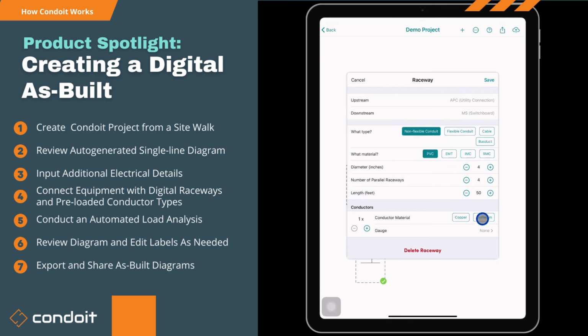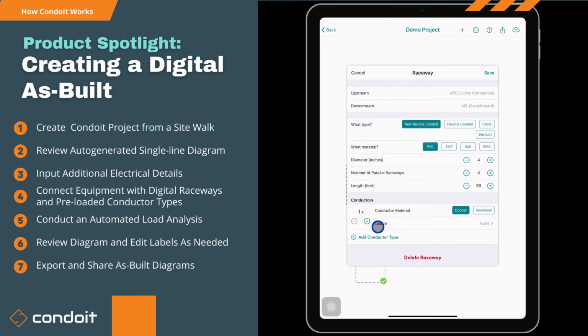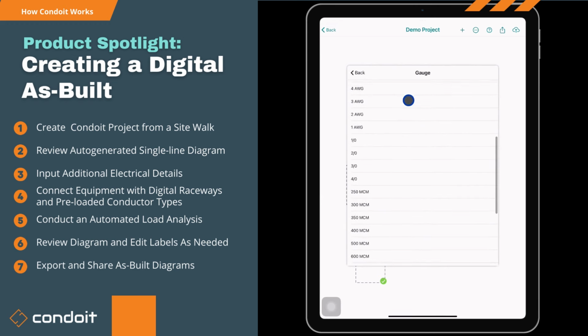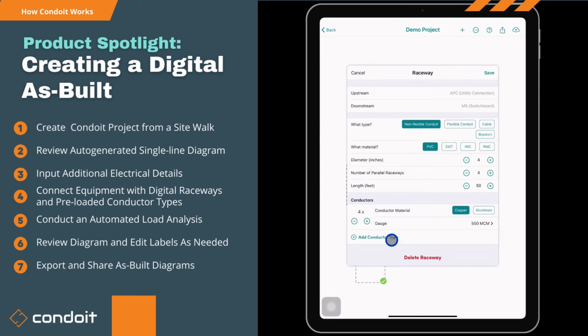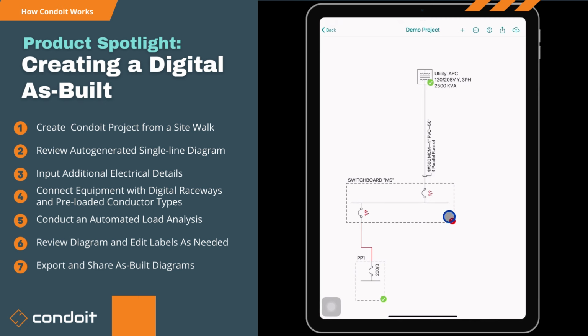And then down here we can say, okay, this is a copper wire, and we'll say that there are 4 500 MCM sizes in here. So we've got all the standard sizes in here. We're going to say that this is 500 MCM. If you've got like another ground that's a different type, you can add it right here, and it's just going to give you the same interface to add another conductor. But I'm going to hit save here. And now we've got 4 parallel runs of 4 500 MCM in 4-inch PVC that is 50 feet long. See that? It'll label that raceway for us.